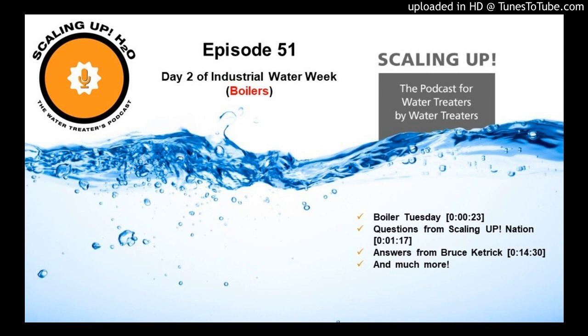Below the 300 psi is the standard. We have dispersant, we have an oxygen scavenger, we maintain an alkalinity of a minimum 200 to 250 OH and a condensate return based on the type of system.